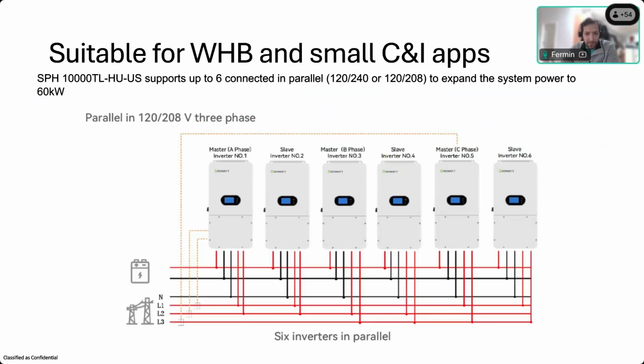In this configuration, you just need to set one of the inverters as the master and the others as slaves, and then you'll only need to adjust the settings or commission the system on the master inverter, and all the others will follow all the settings for that inverter.